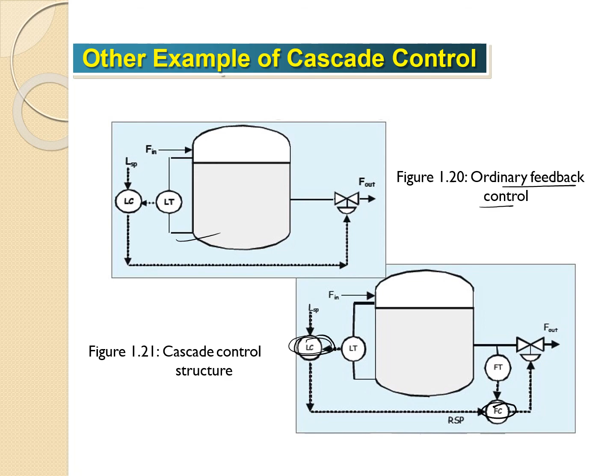So, analysis of figure 1.20 and 1.21. Without the cascade level controller, a change in downstream pressure will disturb the tank level. With the cascade level controller, a change in downstream pressure will be absorbed by the flow controller before it can significantly affect the tank level, because the flow controller responds faster to this disturbance than the tank level process. So basically the purpose of the cascade level controller is to cater to any other disturbance that may cause fluctuation, changes, or instability of the system.